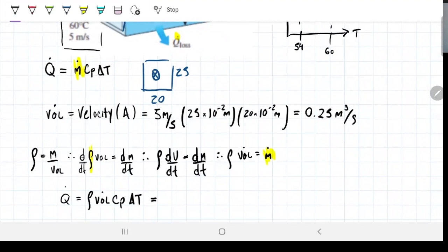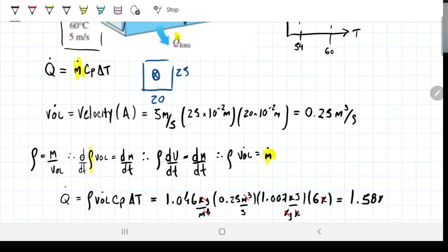So our Q loss will be density times the volume flow rate times the CP times the delta T. And guess what? We have everything. We have density, 1.046 kilograms per meters cubed. We have the volume flow rate, which is 0.25. We have CP, 1.007. And we have the difference in temperature, which is 6 Kelvin or Celsius, being a difference in temperature. My Kelvin goes away, meters cubed go away, my kilograms go away, and I'm left with kilojoules per second, which is the same thing as watts. And I get 1.58 kilojoules per second or kilowatts.